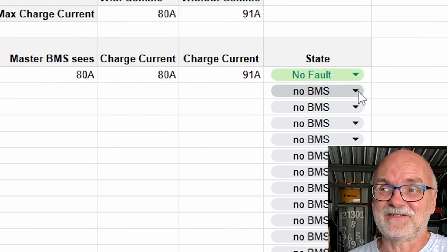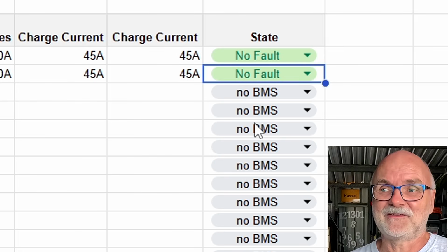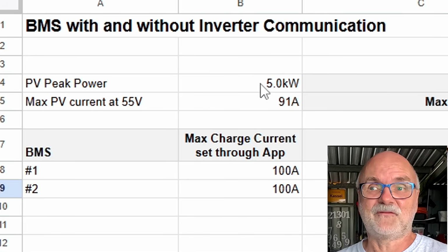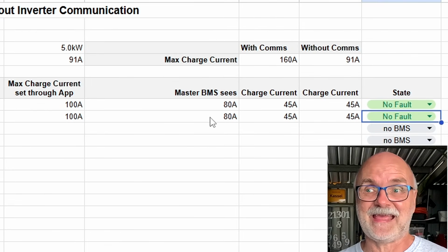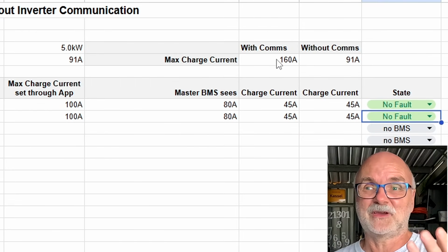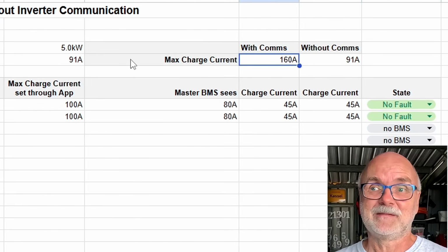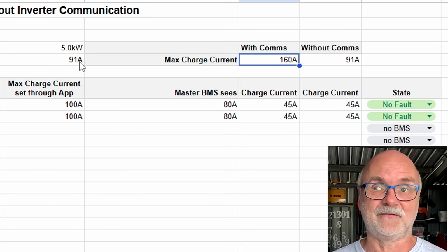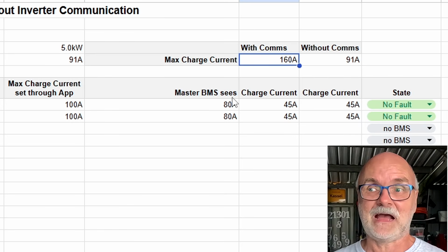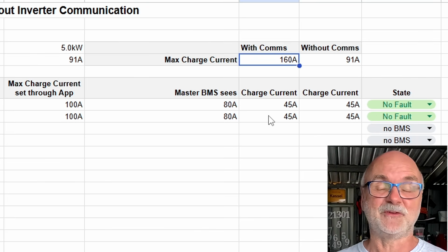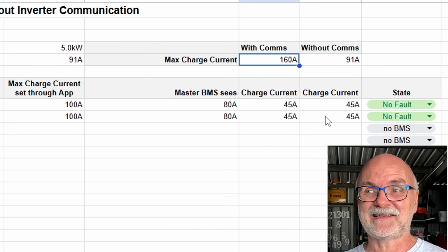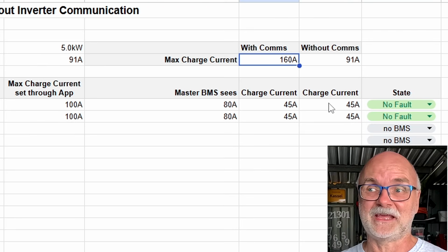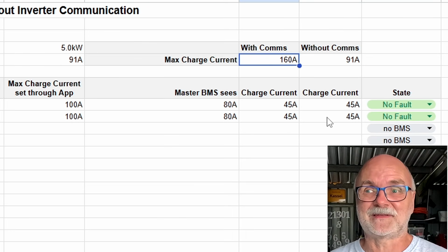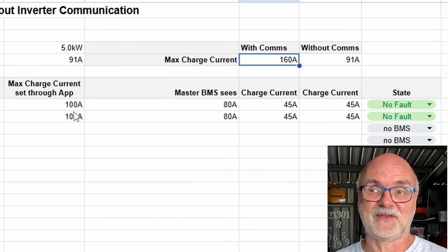So let's introduce a second BMS now. We say this one has no fault. And we still have the 5 kilowatt system, 91 amps. And now the master BMS sees two BMSs, 80 amps, and reports, well, you can charge me with 160 amps. But of course, your solar system can only deliver 91 amps, and this splits up into 45 amps into each of the batteries. And this would be exactly 100% the same without communication, 45 amps into each of the batteries. This is the maximum your solar system can deliver, and it is safe to do because you have set 100 amps.